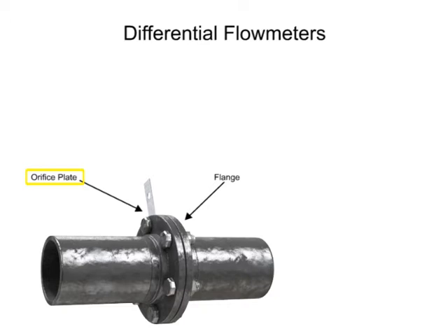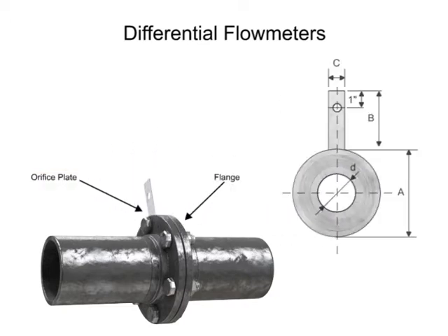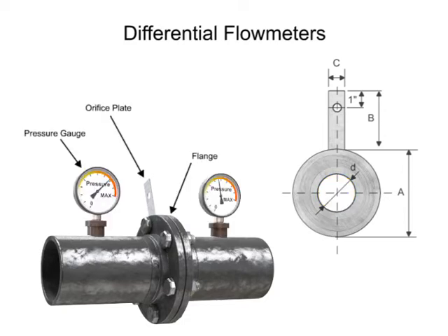The orifice plate of the flow meter is comprised of a circular metal disk with a specific hole diameter that reduces the fluid flow in the pipe. Pressure taps are added on each side of the orifice plate to measure the pressure differential.